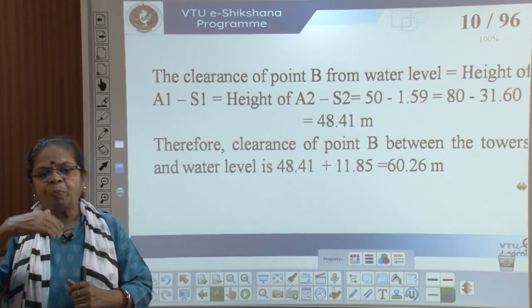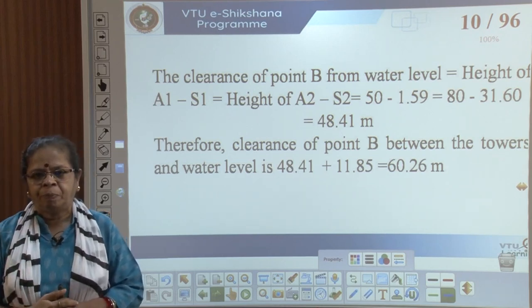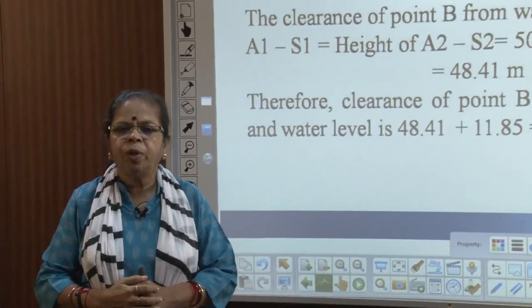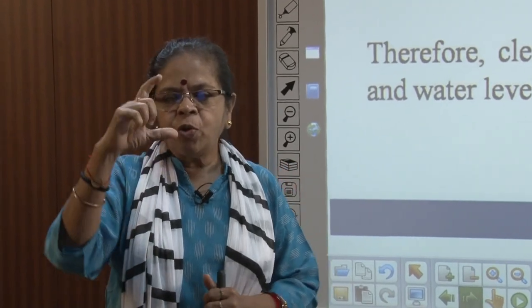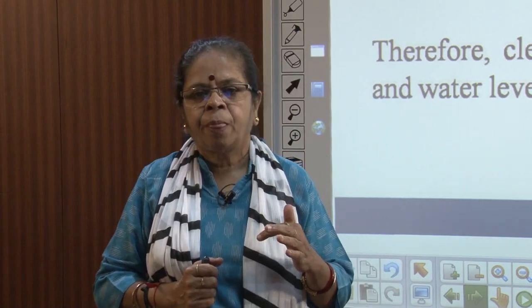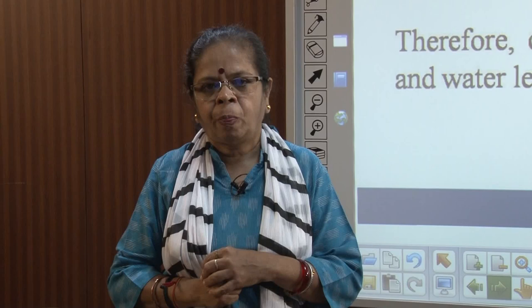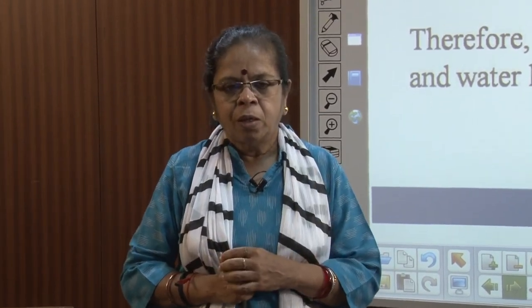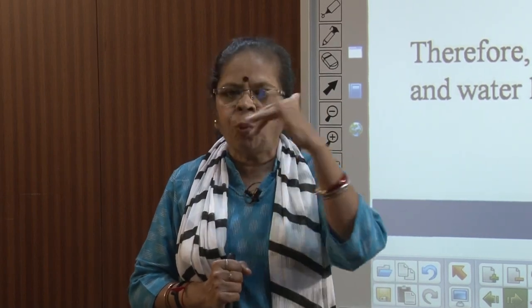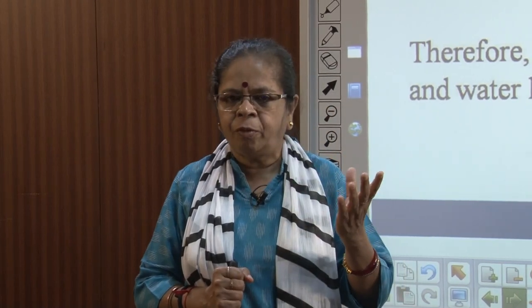Whenever you want to solve problems with supports at different heights, first draw the figure — that is very important. Once you have the figure in place, you will know what distances you need to calculate. The procedure: find the difference between the heights of the towers, calculate A1 and A2, decide whether the lowest point of the catenary lies within or outside the span, then from A1 and A2 get S1 and S2 — the vertical distances of the two supports from the lowest catenary point. Draw the figure correctly and calculations become simple.